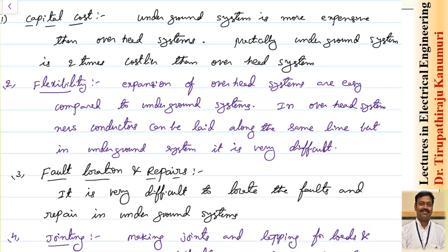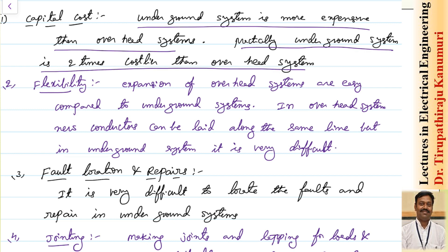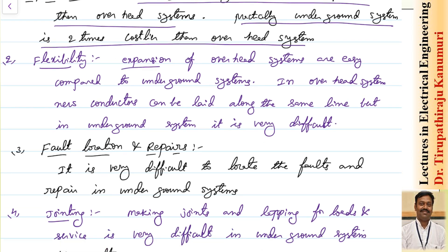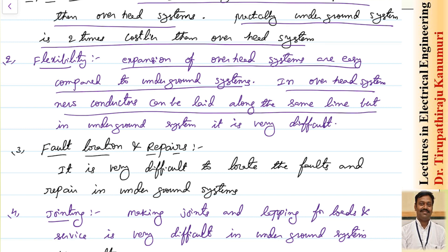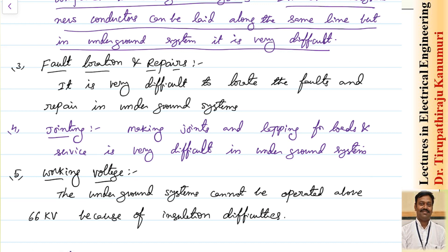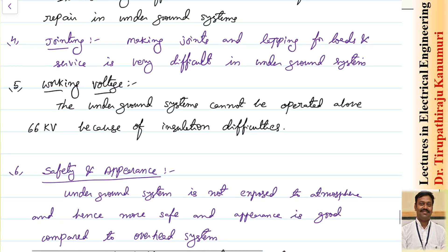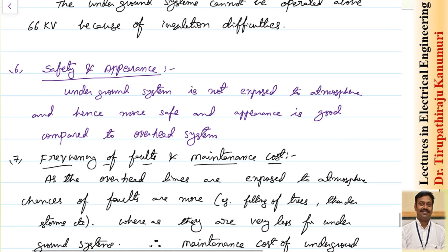Summary of what we have discussed: First, capital cost — underground cables are more expensive than overhead systems; practically the underground system is two times costlier than the overhead system. Second, flexibility — expansion of overhead systems is easy compared to underground; in overhead systems a new conductor can be laid along the same line, but in underground systems it is very difficult. Third, fault location and repairs — it is very difficult to locate faults and repair in underground systems. Joints and tappings are also very difficult in underground systems.